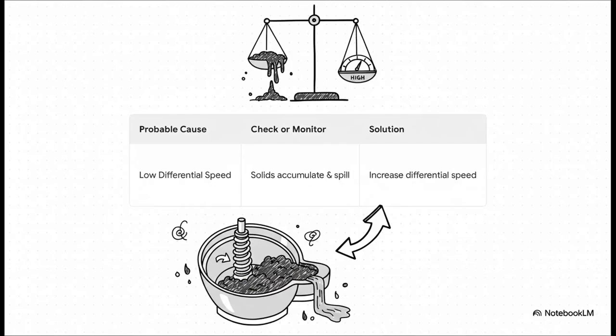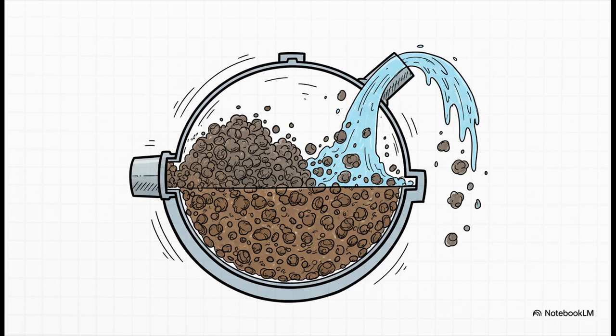See, when the differential speed is too low, that scroll just can't get the solids out of there fast enough. The bowl literally starts to fill up with dewatered cake, and those solids have nowhere to go but to spill over into the liquid, contaminating your centrate. It really shows you what a delicate balancing act centrifuge operation can be. So the big takeaway here is that a low differential speed creates a solids overload and spillover. It's like a traffic jam inside the machine. The dewatering is happening just fine, but you can't get the cake out the door fast enough, and everything backs up.